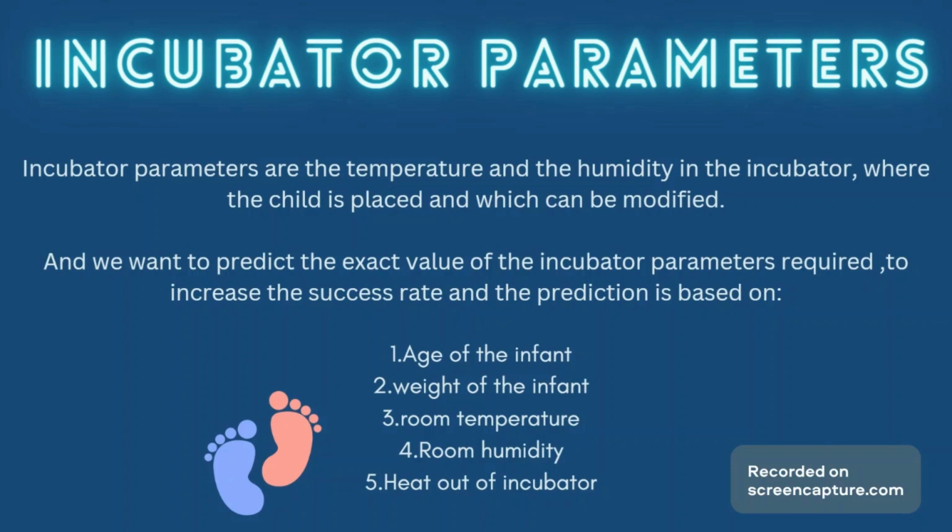We want to predict the exact values of the incubator parameters that we are going to set. The input that we take from the user is the age of the infant, the weight of the infant in grams, the room temperature, and the room humidity, because if the surroundings are not at a constant temperature and humidity and vary, of course it will vary the temperature needed inside the incubator for optimum working as well. Then heat out of the incubator.